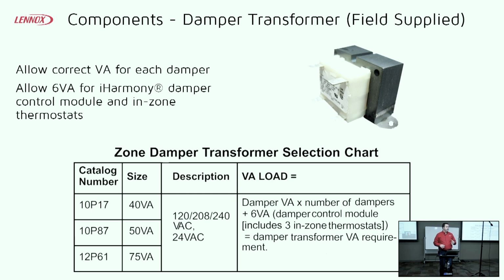Now the important thing is to make sure we have enough capacity out of this transformer. They list some part numbers here for a 40, a 50, and a 75 VA transformer. Essentially, like it mentions here, the damper control module and 3 in-zone stats are going to handle 6 watts, 6 VA. It's the same thing. So when you're sizing these systems out, if you've got, let's say, a 4-zone system, and just to throw a number out there, sorry to make you guys do math this early in the morning, promise it'll be easy.